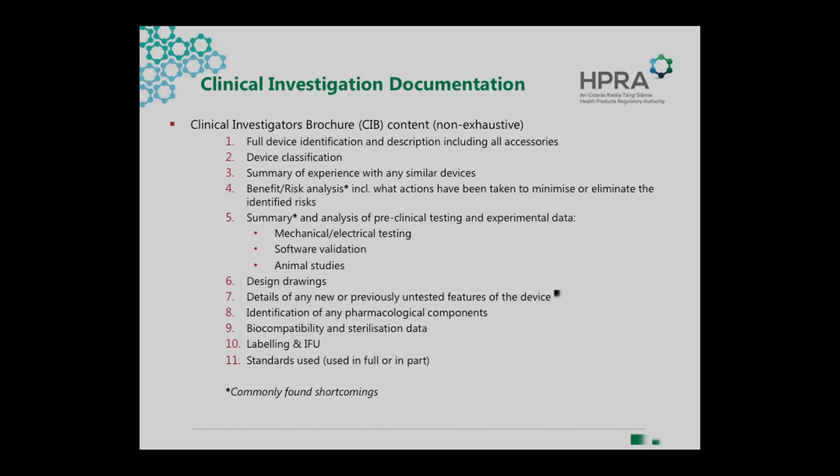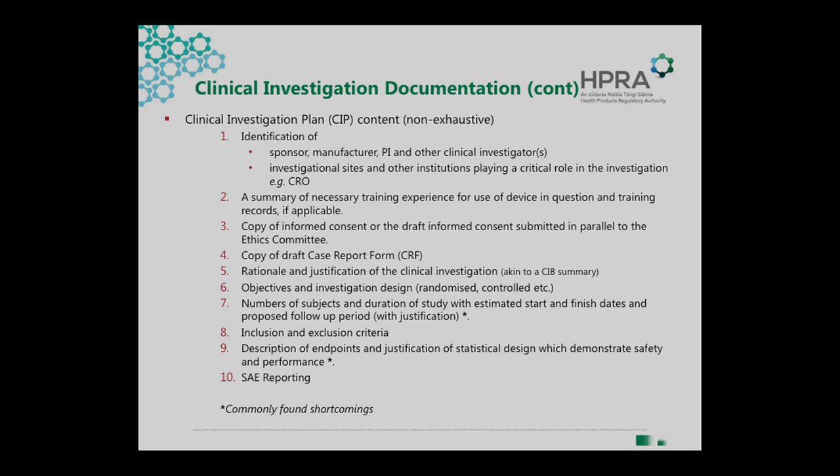At Day 30 to 40, we've sent our questions back and the sponsor has an opportunity to review them. This is where we often get clock stops. We have seen devices submitted to us too early because the sponsor may have to return and do significant testing — perhaps they hadn't looked at some essential requirements that need to be covered, and had to go back and repeat or conduct biocompatibility testing for the first time. This may take more than the two to three months we'd expect a clock stop to be. Once we've reviewed the responses, it goes to the management committee for review, and you would receive your letter of no objection, authorisation, or objection. We update EUDAMED with the outcome, and once there's no objection, you enter the SAE reporting and status update phase. If there is an objection, there is a chance to appeal.